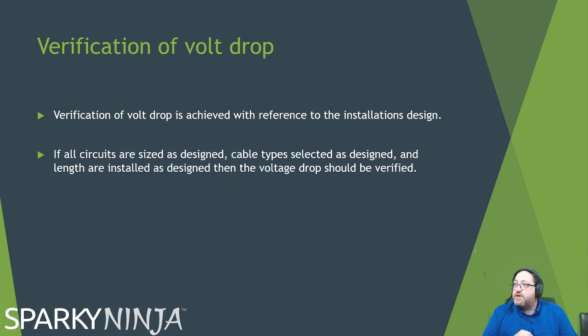We also have verification of volt drop. It's a test. With initial verifications though, it's not a test. What it is, is verification that the designer's information is right. So the designer has designed a system with this cable, this route, this system, this method, blah blah blah, and you go, yep, that's right. Then volt drop's already accounted for, so it shouldn't need to be done. If you do need to do it, then there is a method of measurement using R1 plus Rn and 1.2 and all that stuff. And I can give information on that, but that's outside of the scope of this course, and I don't want to overdo it.